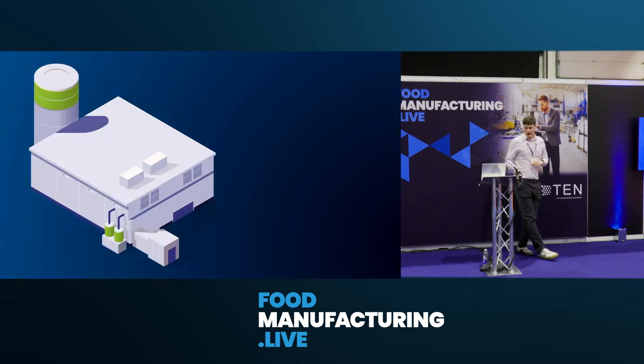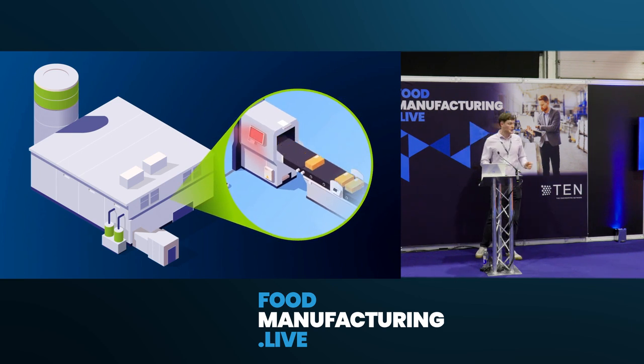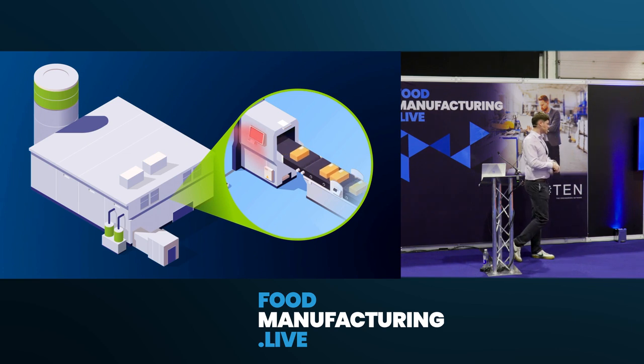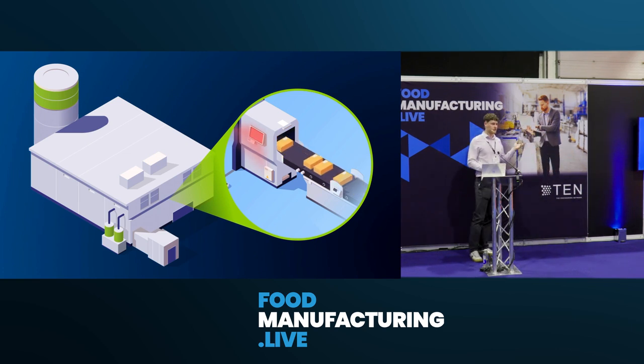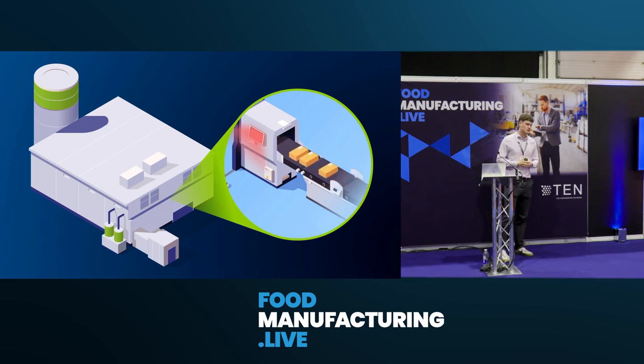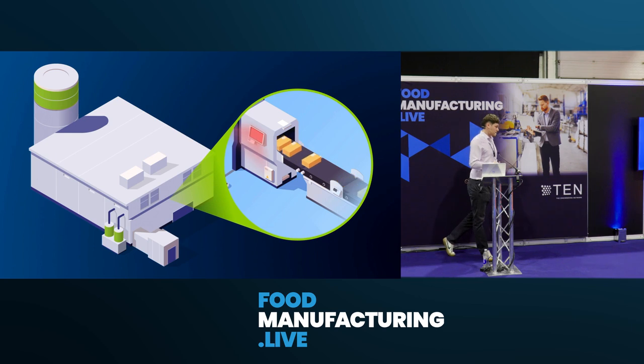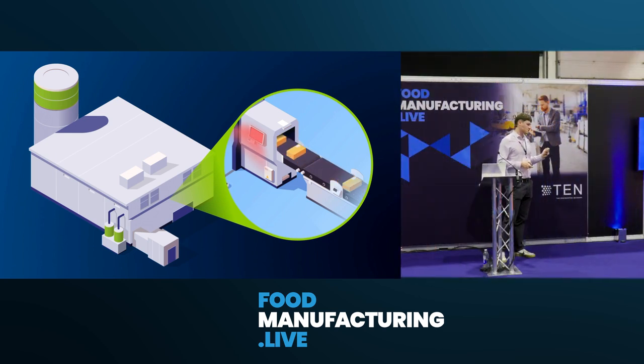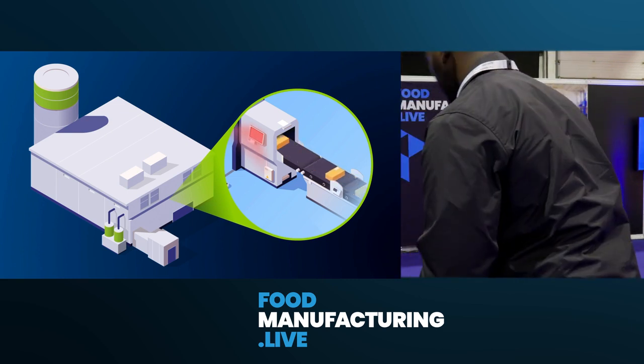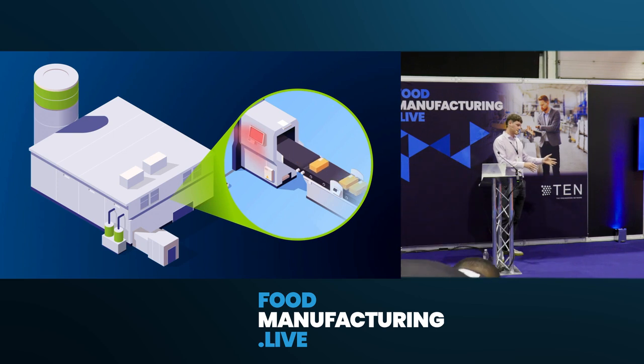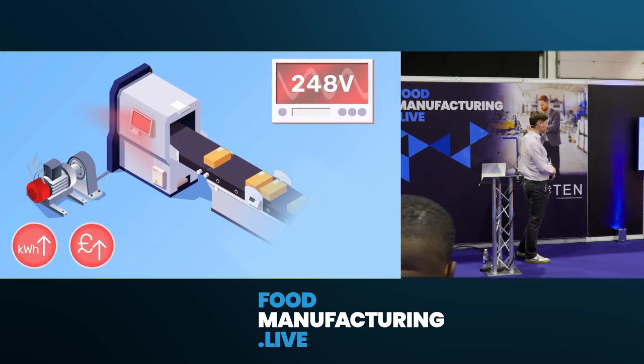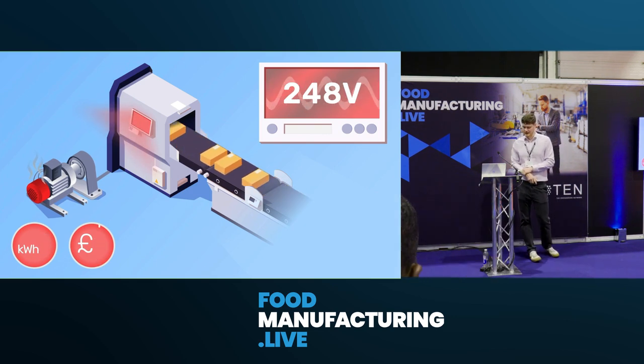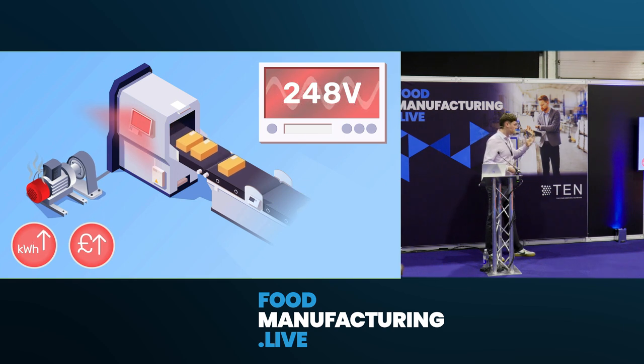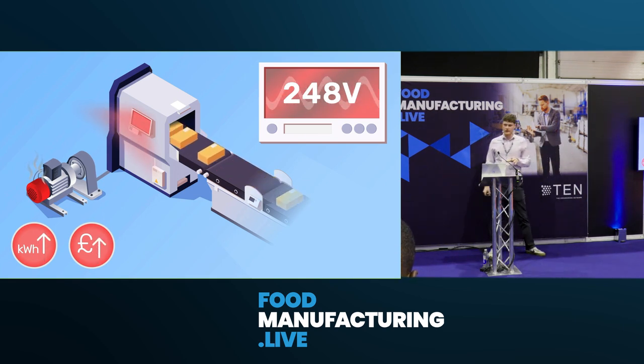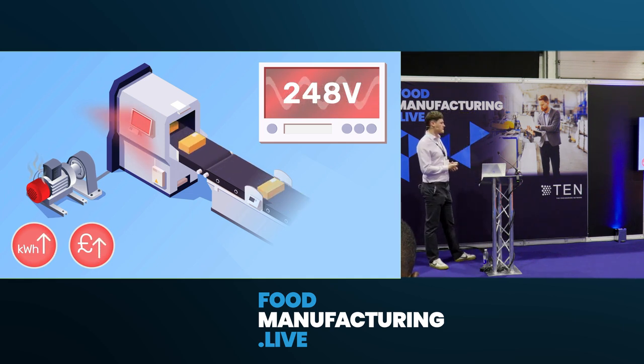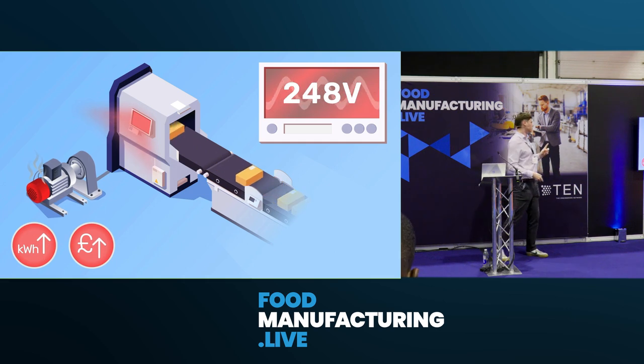So how does it work? We've got a factory, we've got a processing line here. So we've got no voltage optimization on this factory, and we've got outdated transformers on site. So typically doing the 11 kV to 433 volts. Equipment in the UK that is CE marked has been designed to the IEC standard and designed to run at 400 volts. That is what it should be. So when people say, oh, I've got 3 pin, I've got 240 volts, it shouldn't be, it should be 220. That's what the standard says. So by having this over voltage and this oversupply of voltage, that motor's getting quite hot, running not particularly efficiently, burning excess energy. So by going with that VO, reducing that voltage from that 248 volt average that we see, allows the device again to run more efficiently. So 220 volts, remember that number, because that's quite a key number that we target.